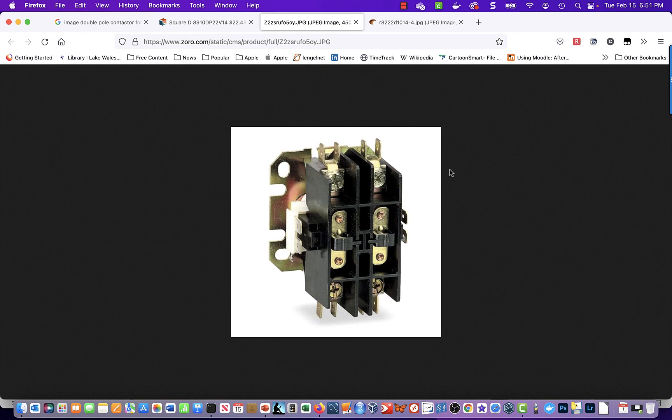A couple additional pictures I want to show you on this video. This is an image of a double pole contactor. These contactors basically work in tracks from top to bottom. On the top terminals on the left and right side, you would attach like L1 and L2. On the bottom terminals would be your output. On each side is where your control voltage connects. There's a block in the middle of plastic that prevents voltage from arcing from one side to the other. When the contactor energizes, the coil, which is at the bottom, pulls down on the two tabs seen in the middle. That's a contactor example.